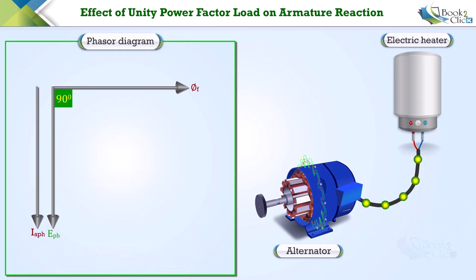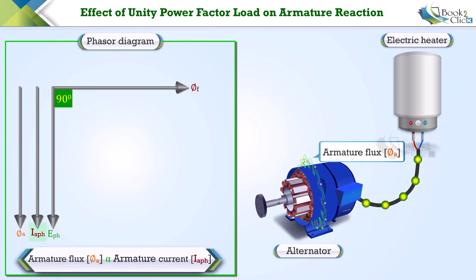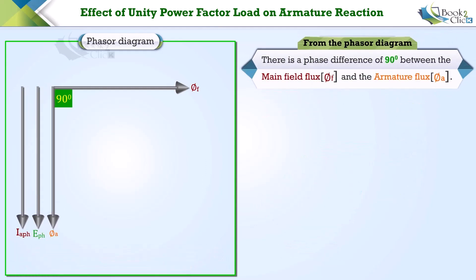So to represent i_aph in the vector diagram, we can draw a line parallel to e_ph. This armature current will set up the armature flux phi_a. We know that flux is directly proportional to current, hence we can draw a line parallel to i_aph to represent the armature flux. From the phasor diagram, it is evident that there is a phase difference of 90 degrees between the main field flux and the armature flux.